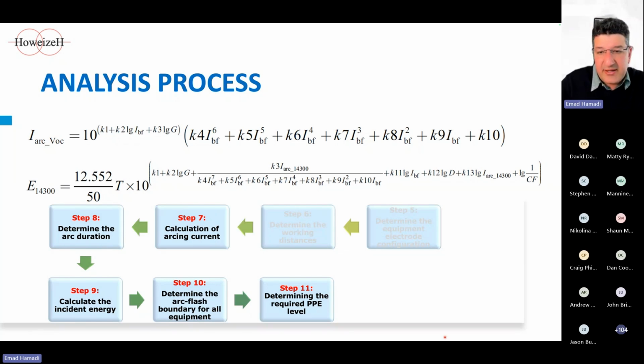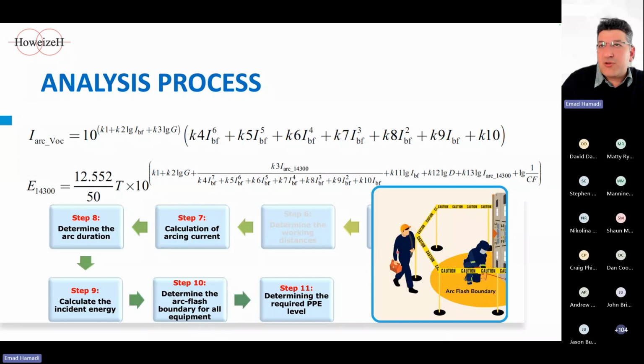The other step is the arc flash boundary, which is defined as the distance at which the potential arc flash will reach an incident energy of 1.2 calories per square centimeter. Why is this specifically important? Because 1.2 calories per square centimeter is considered a safe distance, with minor effect or consequences, and people can actually walk through that without any specific PPE or very low level PPE, let's say. The arc flash boundary is one that you can mark up when staff are working on the live panel.